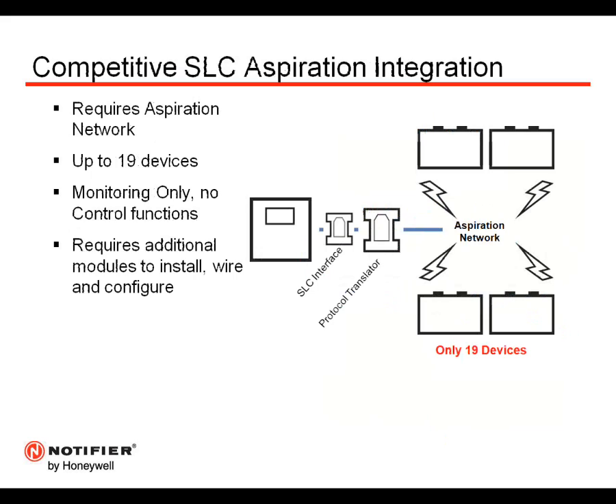We also compare it to some competitive SLC aspiration integration. It required an aspiration network, was good for about 19 devices, but monitoring only. There was no control or read status functions. And if we look at the slide, it also required additional hardware. So we had the aspiration network that would have been required. In this case, there's a protocol translator required to take the information from the aspiration network and translate that protocol. Then it also required an SLC interface. The SLC interface took the information from the protocol translator and made that information available to one of our control panel's SLC loops.